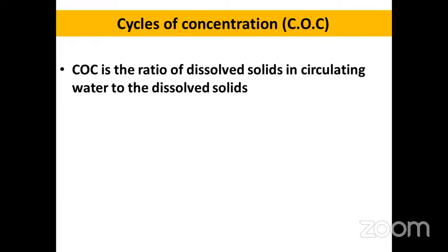Actually, by frequent circulation and cooling, after evaporation, the water gets denser. The ppm will become more in the circulating cooling water. So we have to add water to reduce the dissolved solids in the circulating cooling water. So COC is a main factor for makeup. Because of this, we are blowing it down, and there will be blow down loss.